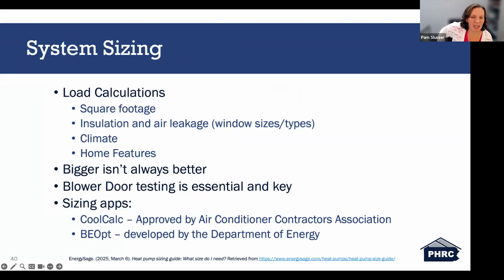But moving along, system sizing, let's talk about this. When planning for a heat pump installation, one of the most important technical steps is completing accurate load calculations. Load calculations tell us how much heating and cooling the home actually needs. And it's not just about the square footage. They also have to factor in the level of insulation and air leakage, which often relates to window size, type, and sealing, and the climate where the home is located. For example, Pennsylvania sees both heating and cooling needs throughout the whole year, and home features like ceiling height, layout, orientation, even how many people live there, all impact the system's required capacity.